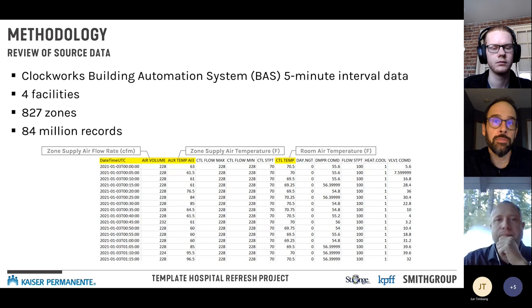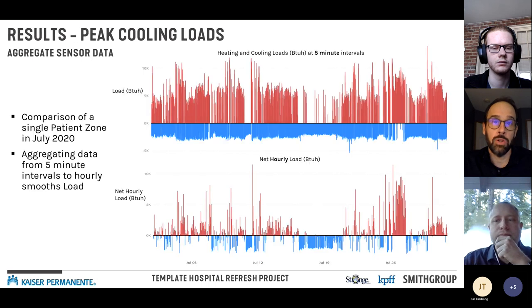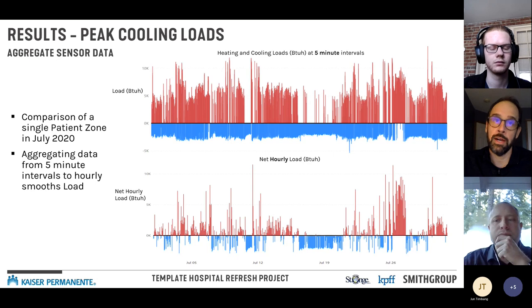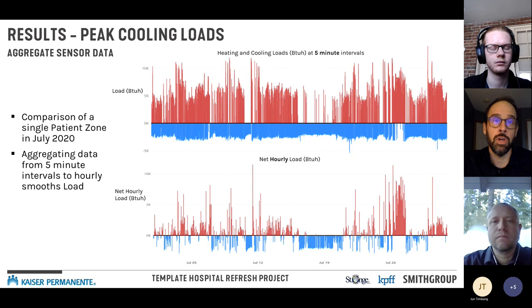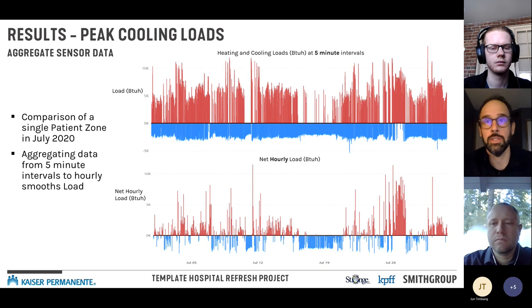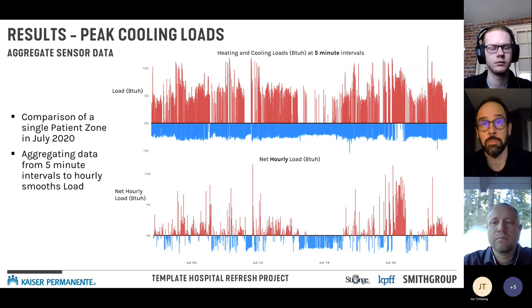Looking at two visualizations of the same data: the top chart shows five-minute interval data for a single zone in San Leandro for July 2020. Each bar represents a five-minute interval, and what we see is rapid flipping back and forth between heating and cooling. This was one of the early surprises — it was expected there would be a distinct heating period and then a cooling period.